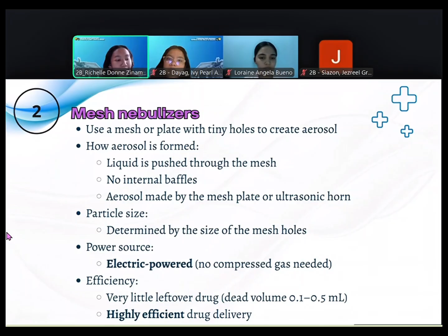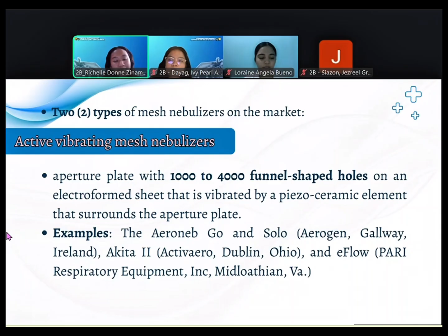Under mesh nebulizer, there are two types. Active vibrating mesh nebulizers have an aperture plate with 1,000 to 4,000 funnel-shaped holes on an electroformed sheet that is vibrated by a piezo-ceramic element that surrounds the aperture plate. Examples of this are the AeroNeb Go and Solo, Aerogen, Galway, Ireland, Akita 2, Activaero, Dublin, Ohio, and eFlow. Next. The other type is the passive. So, earlier was active, now is passive. It uses an ultrasonic horn to push liquid through a mesh.